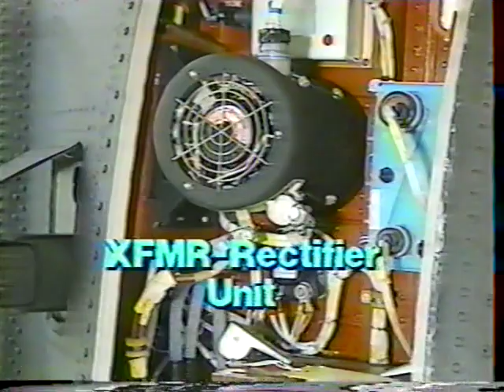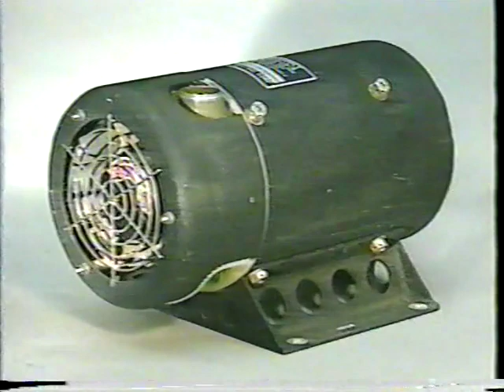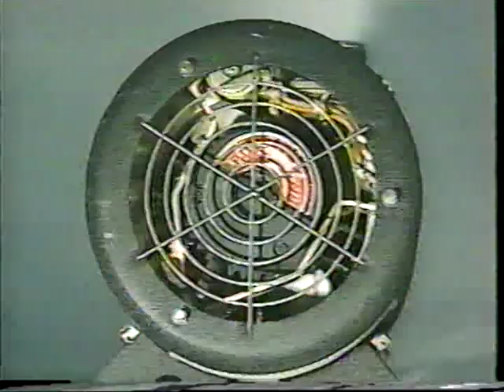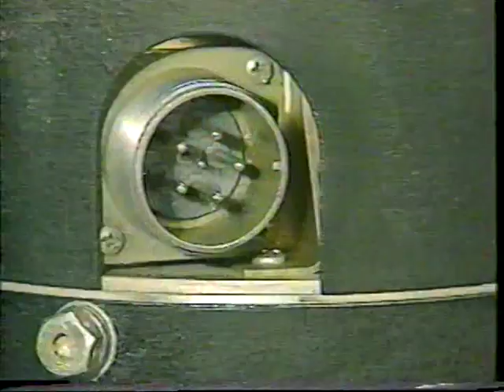The other 2 buses, the number 1 and number 2 DC buses, receive their power from the number 1 and number 2 AC buses by way of transformer rectifiers in the electrical compartments. The transformer rectifier units, or TRUs, operate off 200 volts, 3-phase AC. The transformer in each TRU steps down the 200 volts to 48.5 volts, 3-phase AC. 6 rectifiers convert the 48.5 volts AC to 28 volts DC. Inside the TRU is a cooling fan operated by AC.